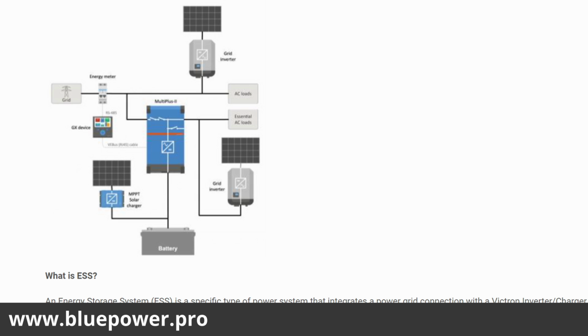This energy meter, must you have this energy meter? No, it's not a must-have. If you want a grid tie inverter on the input, it's a requirement for the energy meter, and you want zero feed-in. So the energy meter just gives you the capability to feed non-essential loads, and on top of that, connect the grid tie inverter on the input. If you connect it only to your essential loads, you don't need it? Yeah, so if you only have all your essential loads running through the inverter, then it's not a requirement for the energy meter. The energy meter is just if you have non-essential loads that you want to measure accurately and feed from your excess solar power.